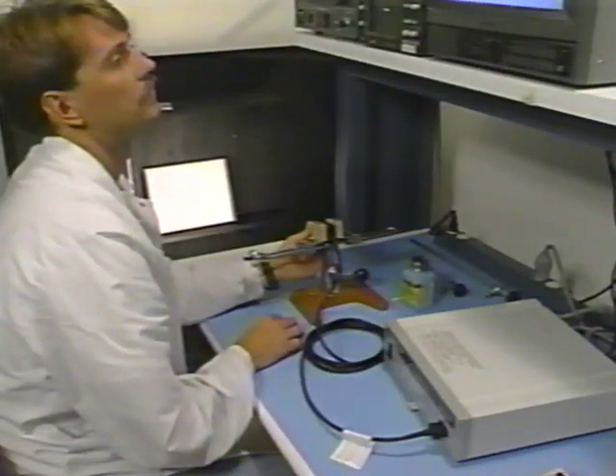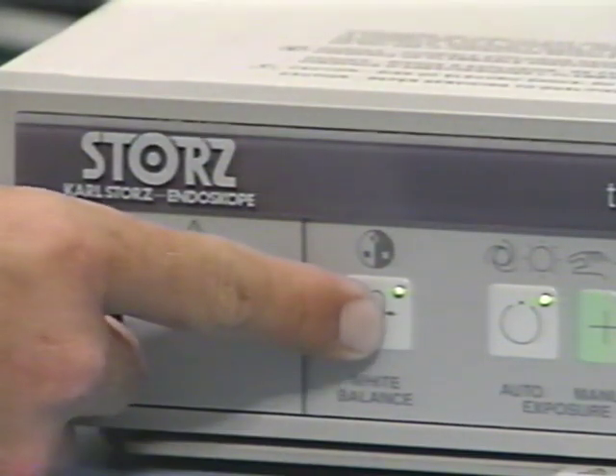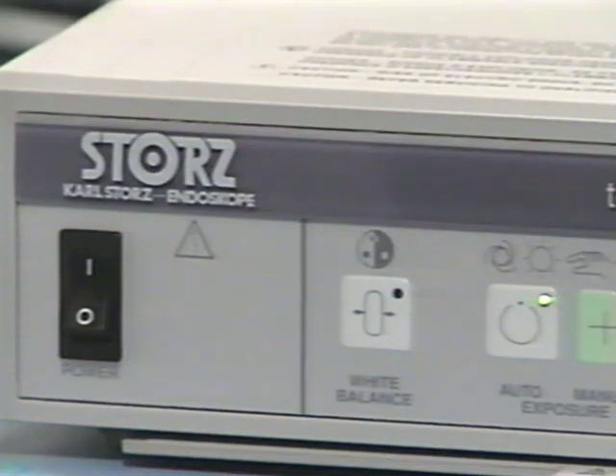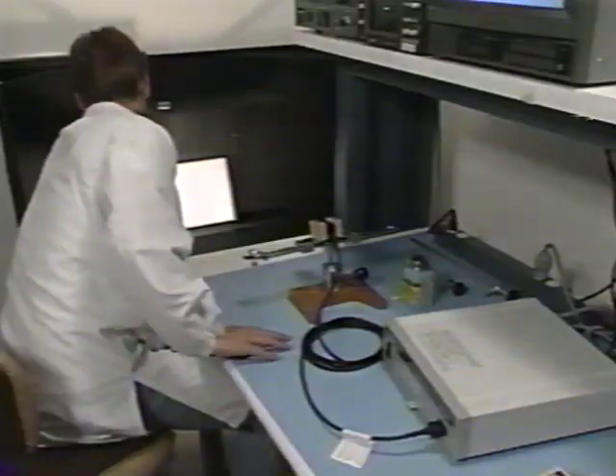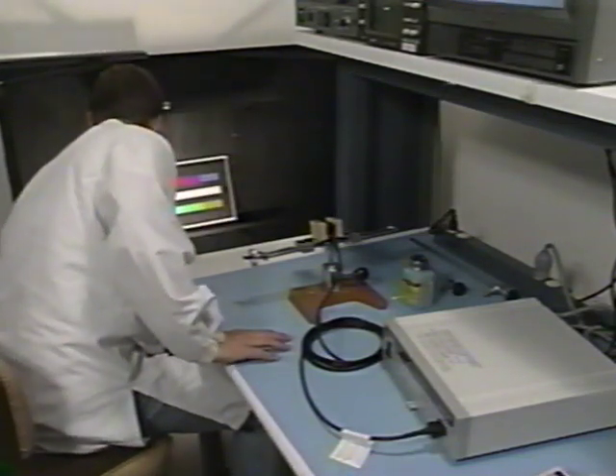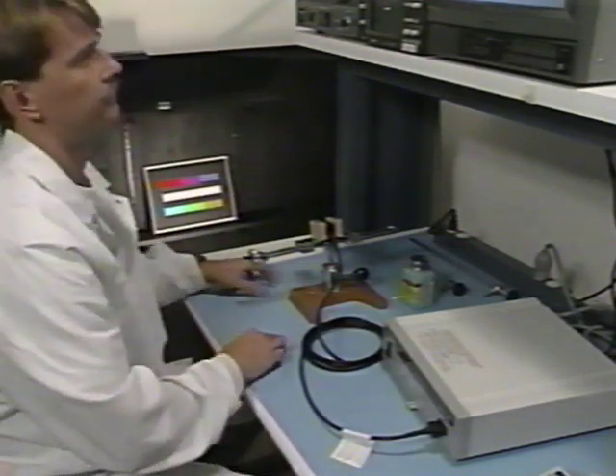Using the white reflectance chart, point the camera at the chart so that the white image fills the monitor screen. Press the white balance button on the front panel of the CCU. A message will appear on the monitor, "White balance OK," with most Karl Storz cameras. Other manufacturers may have different indicators or none at all. If the message "White balance failed" appears, repeat the process, ensuring that the white image fills the monitor screen. Remove the white reflectance chart after white balancing is completed.